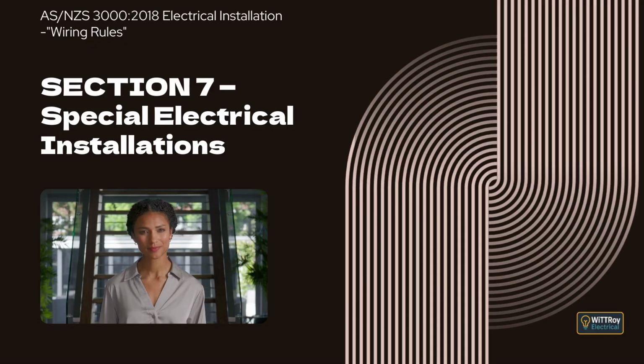This clause explains that where a switch for safety services is installed on a switchboard in an outbuilding, that switch is regarded as a main switch for the purposes of this clause. It also explains that a safety service main switch installed in an outbuilding must be clearly identified in accordance with Clause 7.2.4.4. The clause further explains that any switch located remote from an outbuilding, or operating in the supply circuit to a safety service main switch installed in the outbuilding, must also be clearly identified with the required markings.